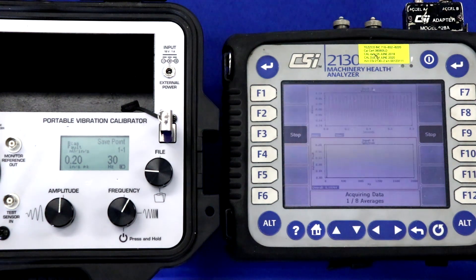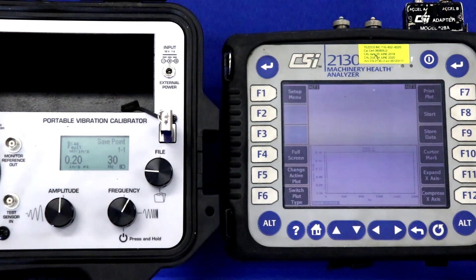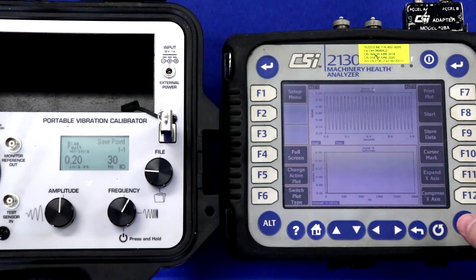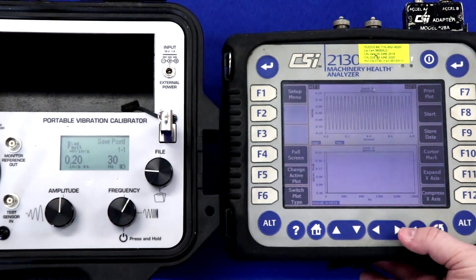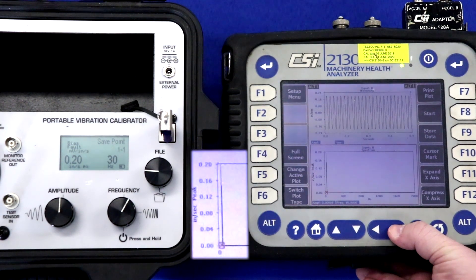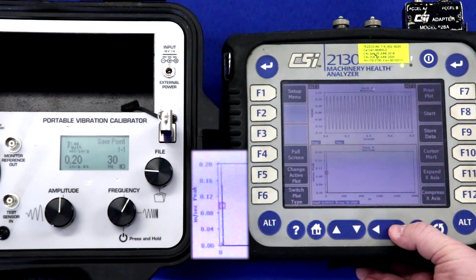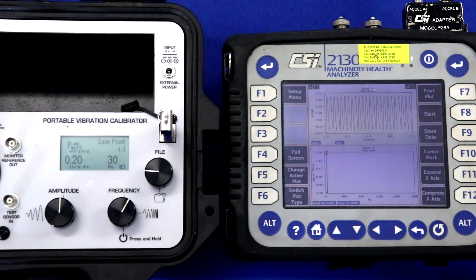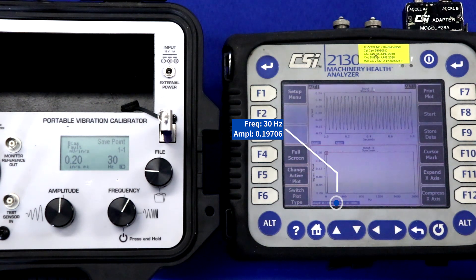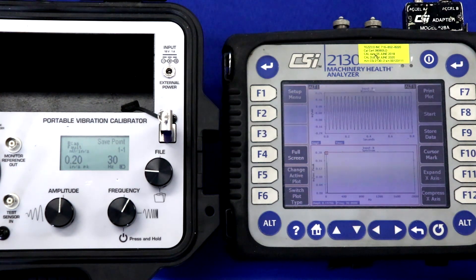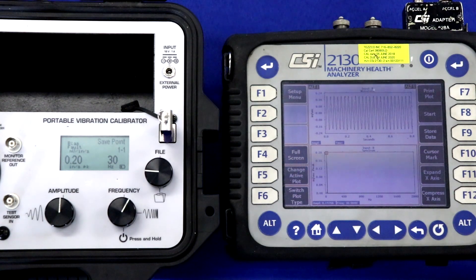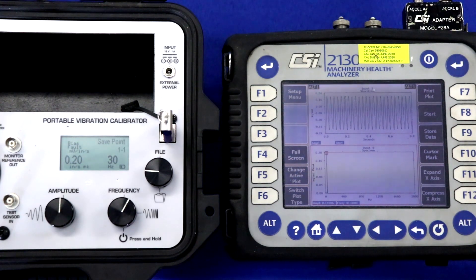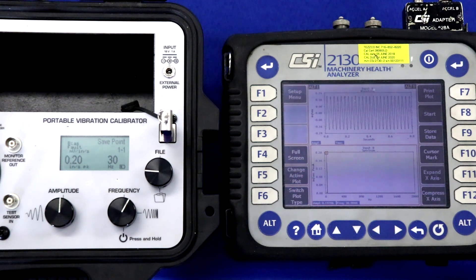Our first test point is at 0.2 inches per second peak, and you saw that I have acquired data and our overall vibration is at 0.197 inches per second. If I scroll the cursor over and center it at the tip of the peak, you can see that my amplitude is 0.197 at 30 hertz. So my frequency measurement is correct, and my amplitude is very close to the known calibration value of 0.2 inches per second peak.